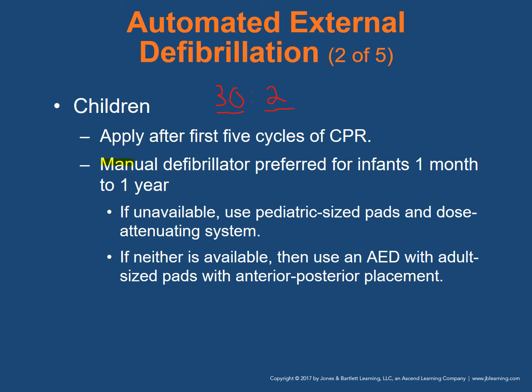What they mean here, the manual defibrillator, is different from the AED in the sense for 2 reasons. The manual defibrillator, unlike the AED, allows us to actually visualize the patient's cardiac rhythm in real time, and the manual defibrillator allows us to adjust the joule setting. In essence, it allows us to manipulate how much electrical energy actually moves through the patient.